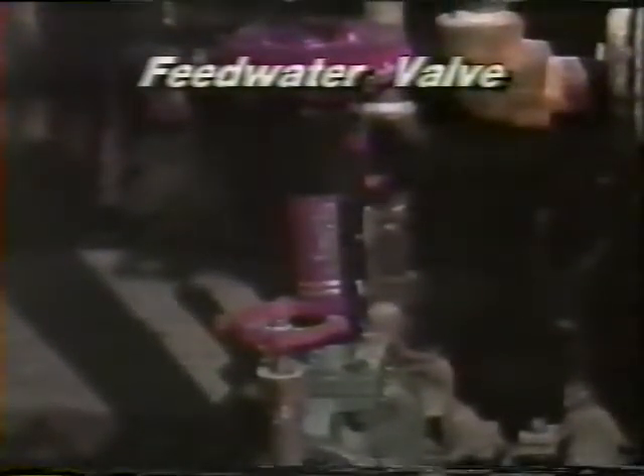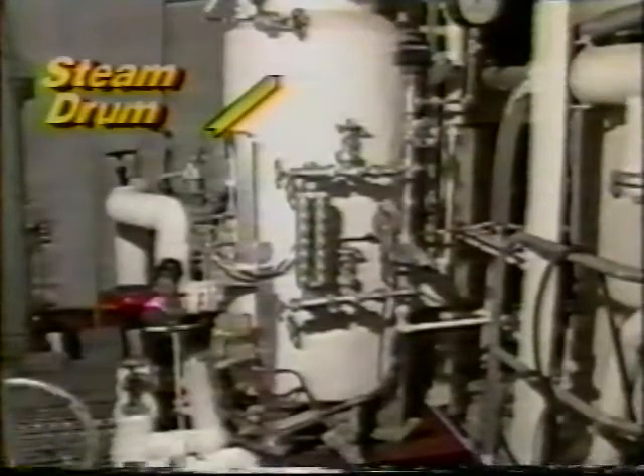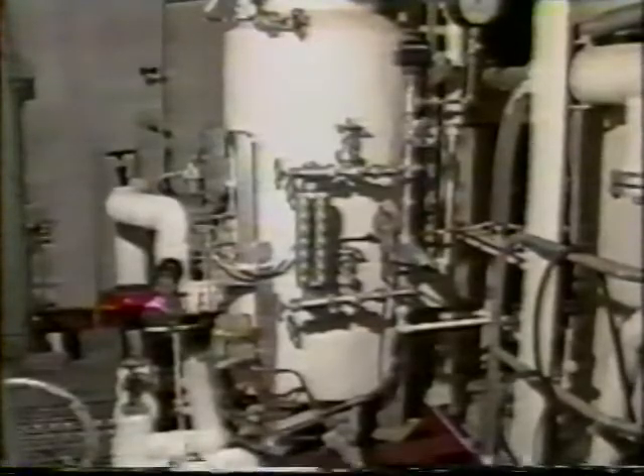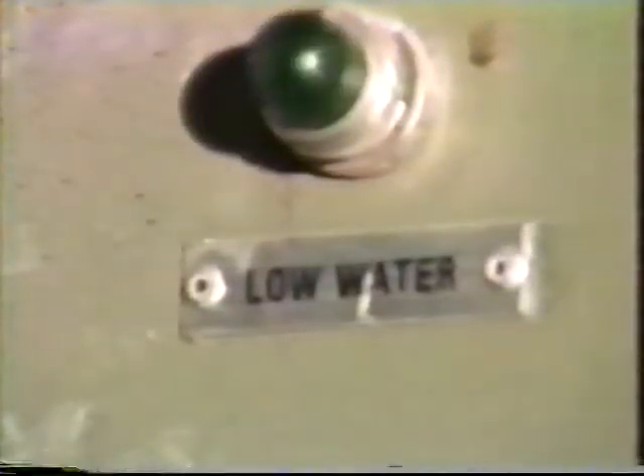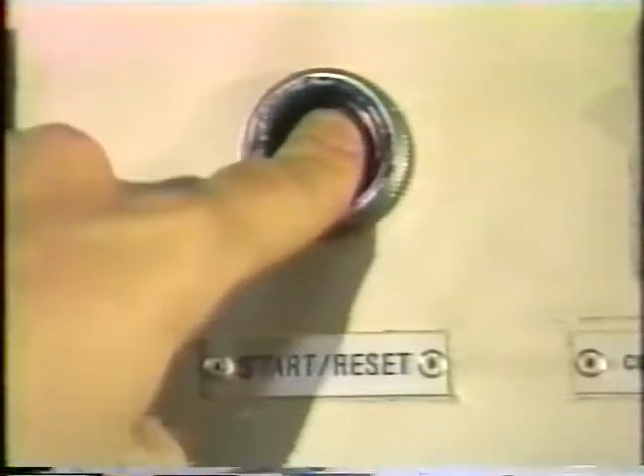With the control circuit powered, circuits are completed to the low water control, alarm horn, low water light, the high water control, feed water air solenoid valve, and the automatic blowdown control. The feed water air solenoid admits air to open the feed water valve, which admits water into the drum. When the water rises in the drum to contact the low water level probe of the low water control, it will energize the low water control. The low water light will then be de-energized. To cancel the alarm horn, the start reset switch must be pressed.